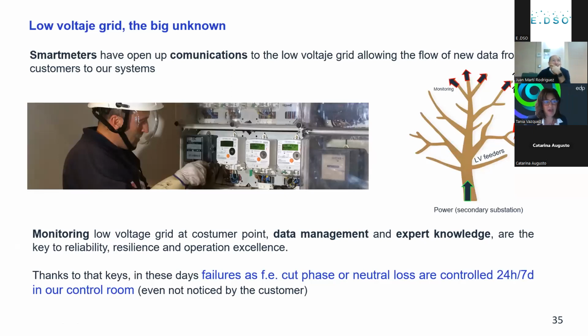Smart meters have opened up communication to the low voltage grid, allowing the flow of new data from customers to our systems. Monitoring low voltage grid at customer point, data management and expert knowledge are the keys to reliability, resilience, and operation excellence. Thanks to these keys, failures, such as cut phase or neutral loss, are controlled 24/7 in our control room, even without being noticed by the customers.